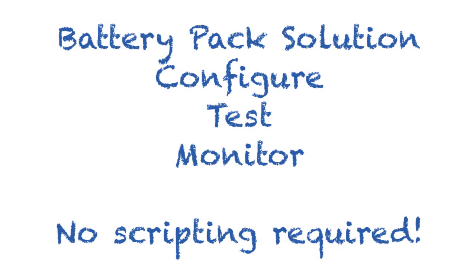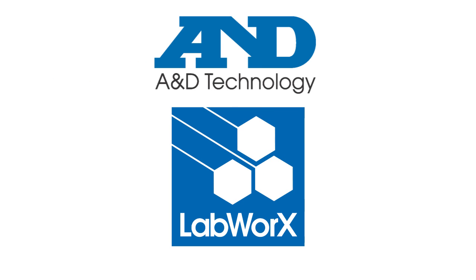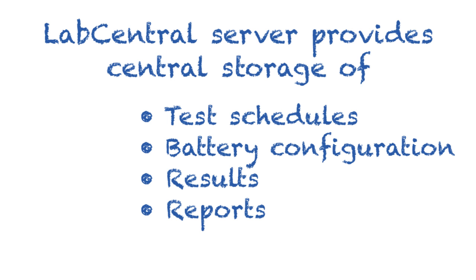An entire battery pack test can be configured, tested, and monitored by entering just a few values through spreadsheets. When used with A&D's LabWorX Lab Management Suite, the test schedules, battery configuration files, results, and automatically generated reports are stored on the Lab Central server for easy access and retrieval across an entire global organization.